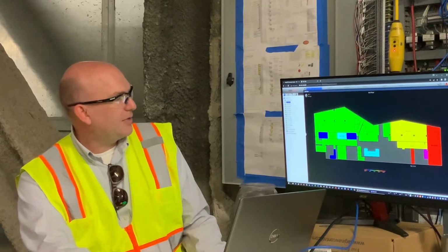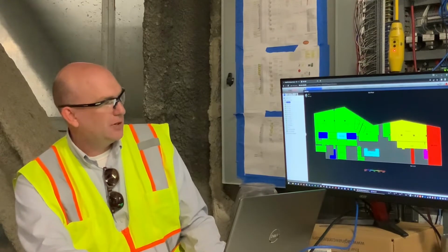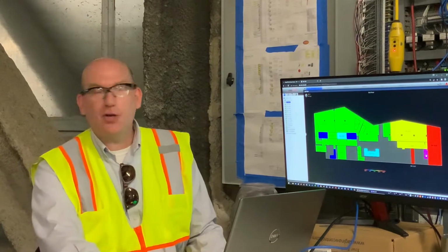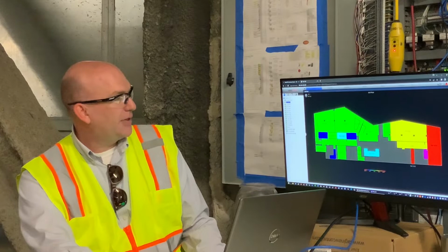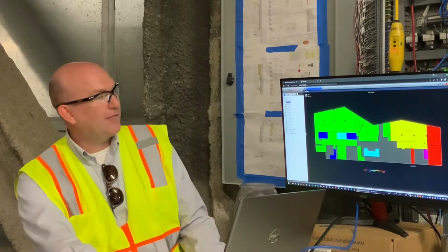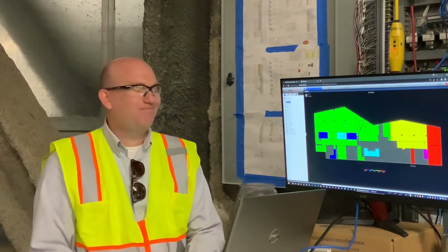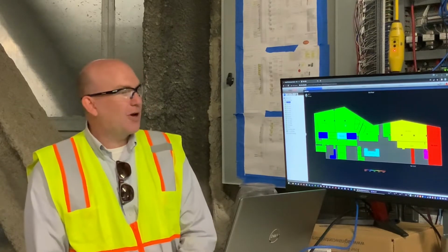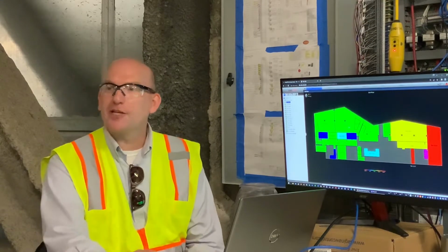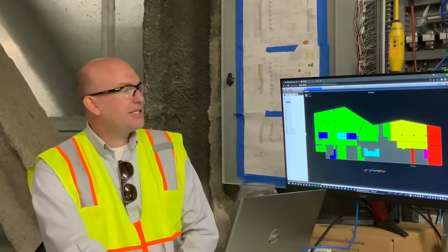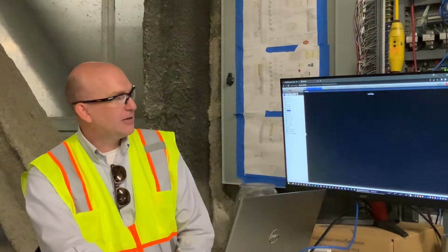Yeah. So the layout that we have, these thermographics are going to give you information about the room. Right here is an indication that we're not communicating to a controller, so they usually show up in a purple color. The other thing that will show up would be any alarms. So if you have an alarm in the room, and let's say the room temperature is where it needs to be, and this room's green, but all of a sudden the VAV fails, okay? And we're not getting the flow we need, and it triggers an alarm. When that alarm goes off, even though it's the right temperature, the whole space will go red, right? So it's an easy, quick way for you to go through and quickly look at the state of a building, right?